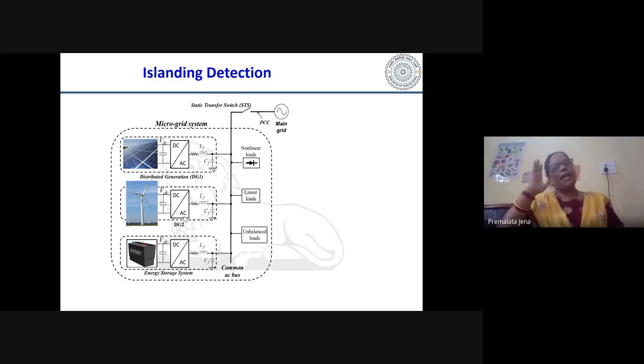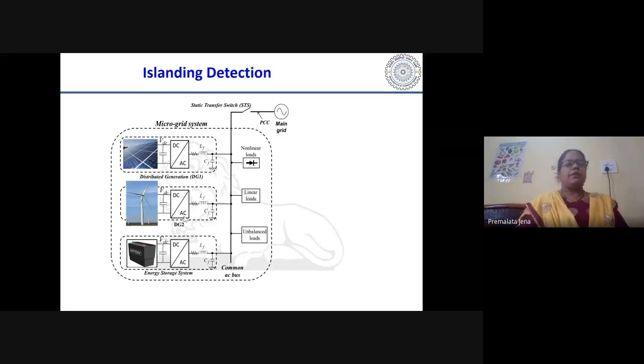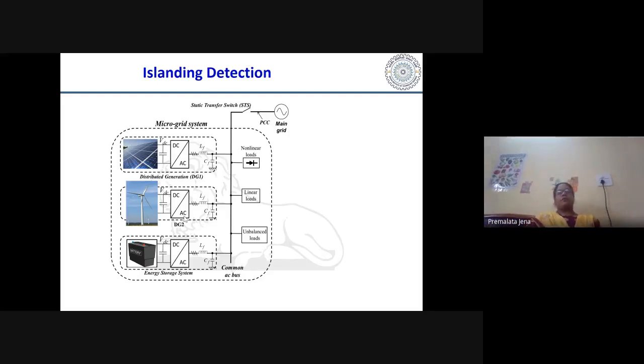All these operations, once I have to detect that the grid is off, that process is known as islanding detection. According to the IEEE 1547 series standard, all of you can write down IEEE 1547 series, this should be detected within 2 seconds. 1 to 2 seconds. In some cases it is also done within 0.3 or 0.5 seconds. It varies from country to country. Like in Canada and Europe, they detect within 0.5 seconds. In the US and India, we detect within 2 seconds. In many other countries, within 0.3 seconds. So it varies from country to country, depending on their network, their size, their load criticality, everything.